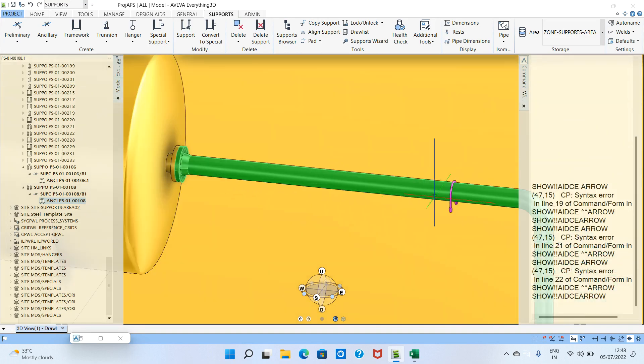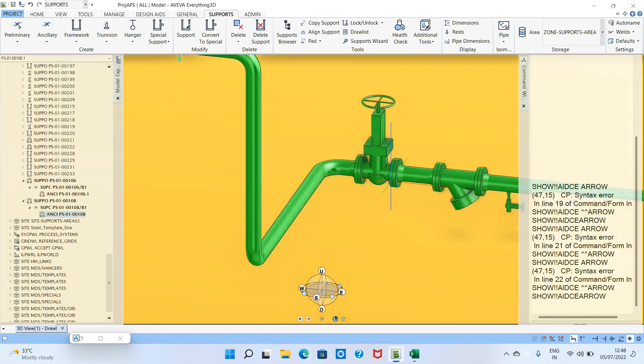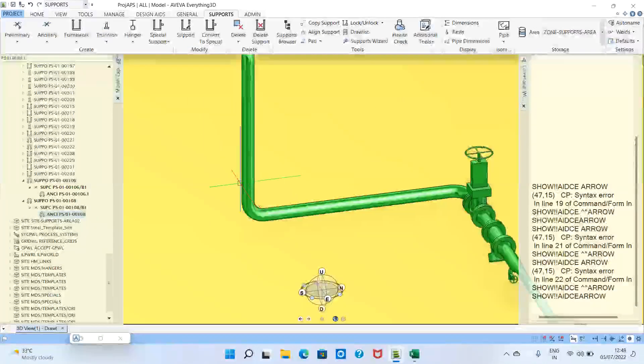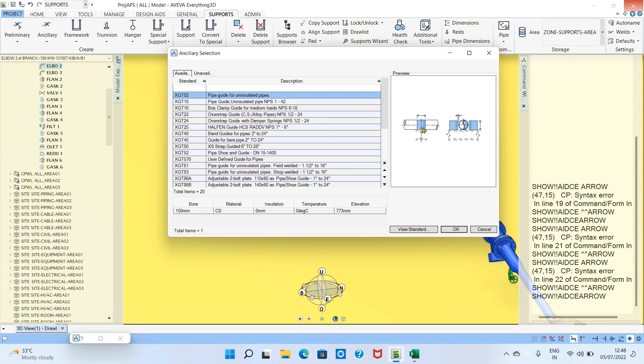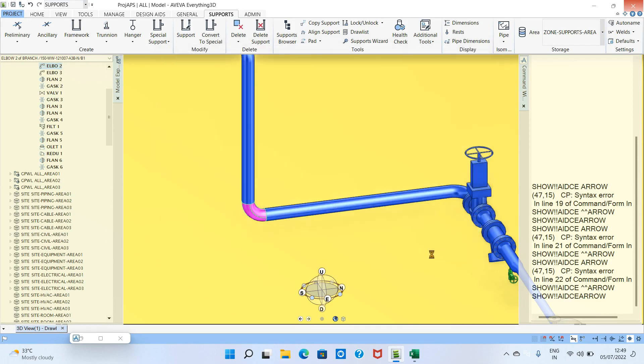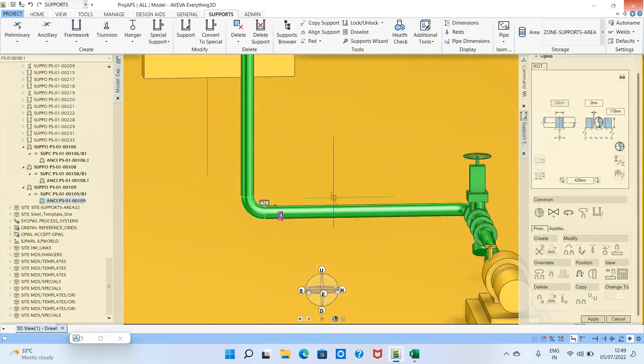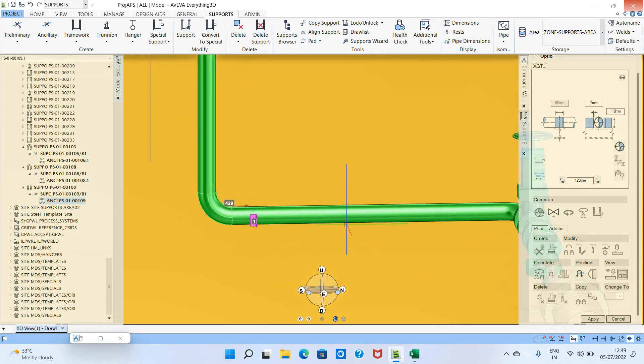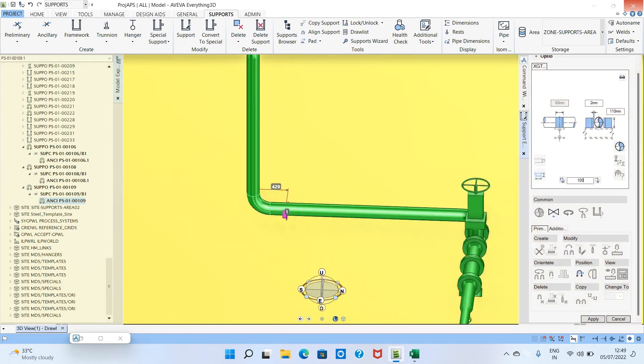Click the support and it will automatically go into the correct zone in the hierarchy. Next, I'll make a guide support near this elbow. Click the elbow, go to Anchor Guide, select the non-insulated pipe option, and click. This is the guide support. The project standards will mention guide supports, anchor supports, and support direction — just follow those. I'll give 1000 mm distance, set the naming, and click Apply.